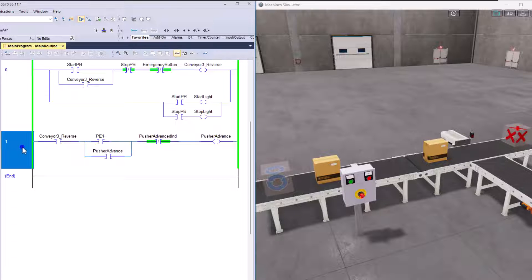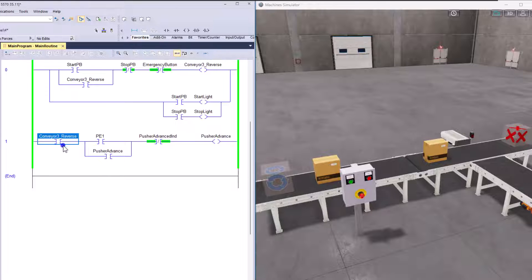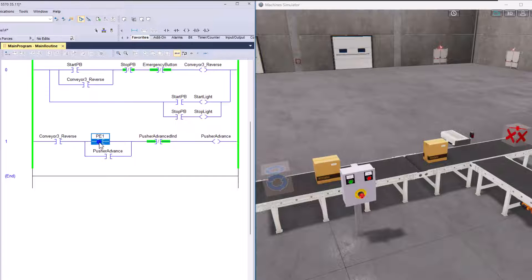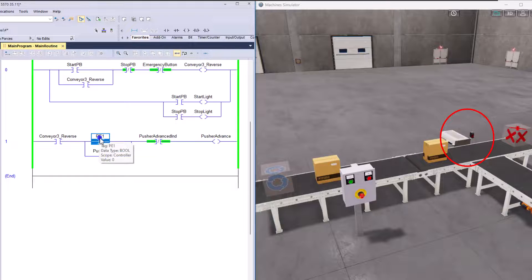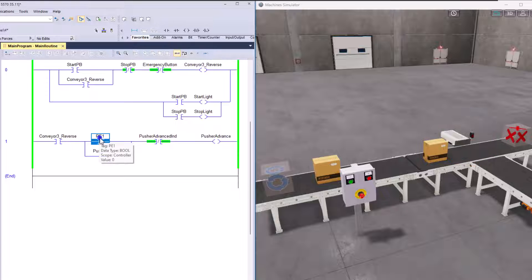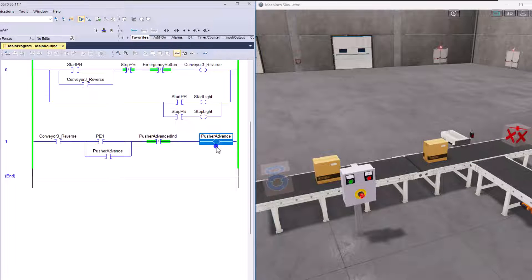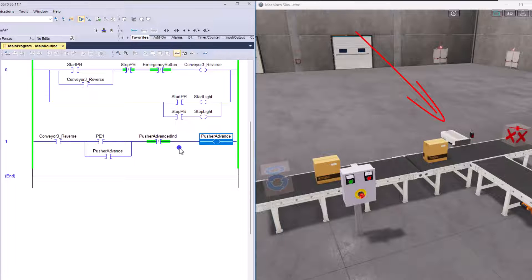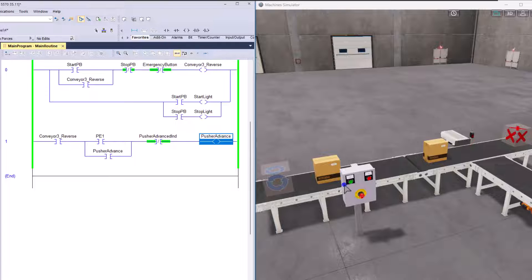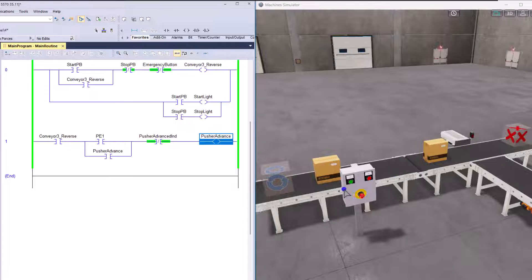Now rung one will actually go in and make sure that the conveyor is running. Then it will say if PE1, which is this PE right over here, the photo eye, right? So photo eye, if it's detected, then what it's going to do is it's going to advance the pusher. So all the tall boxes, what's going to happen is all the tall boxes will get pushed to the next conveyor. And then all the short boxes will continue through the system.